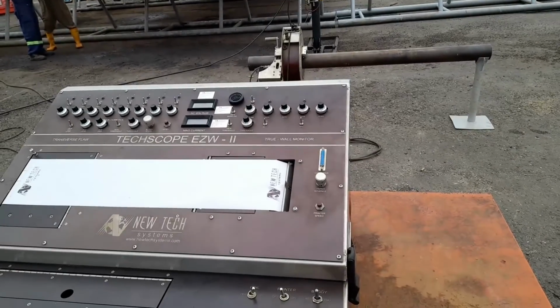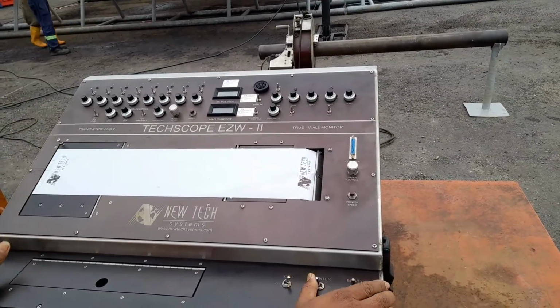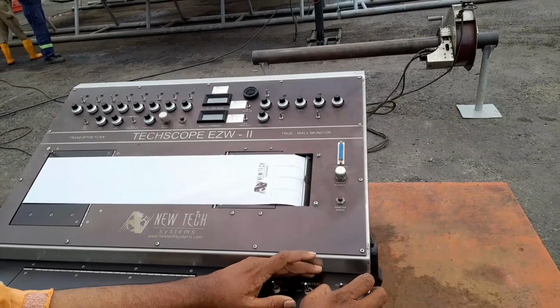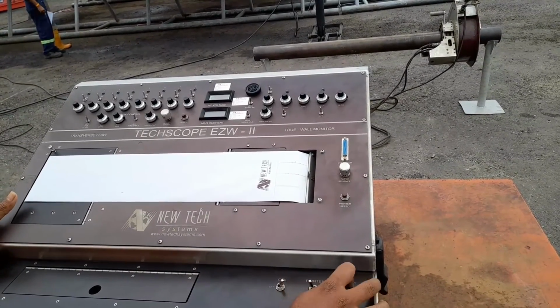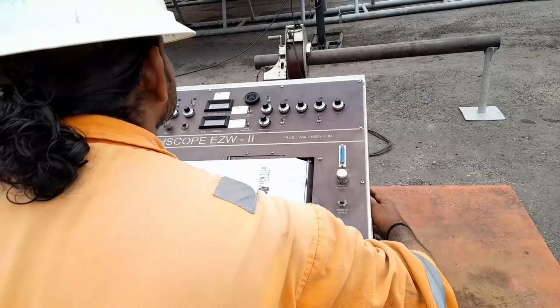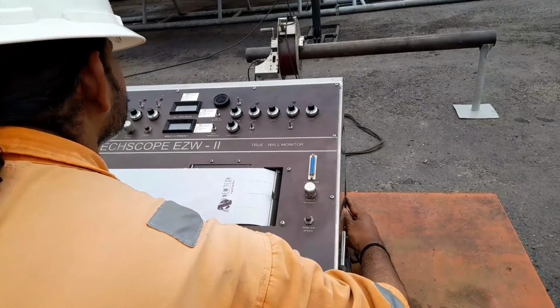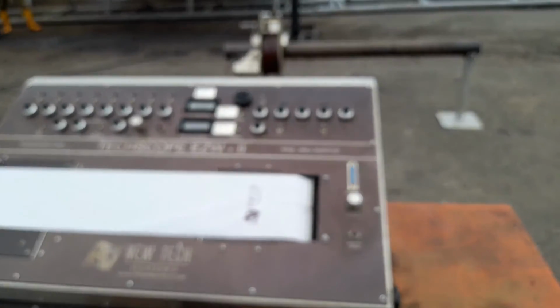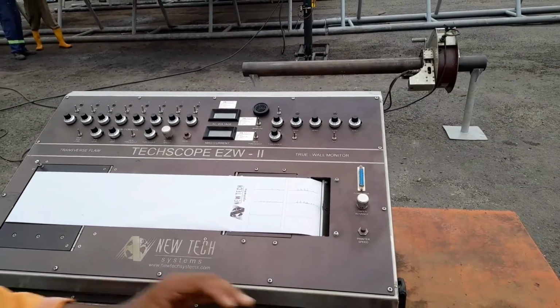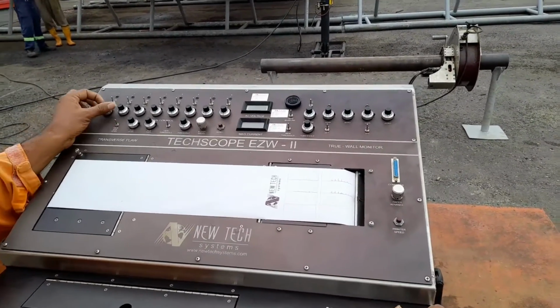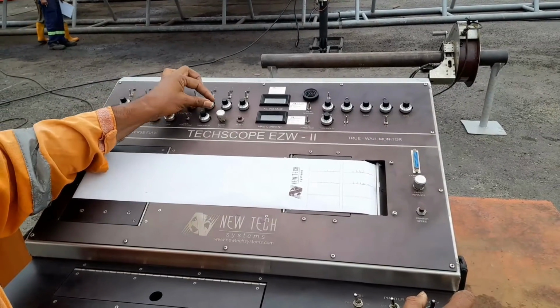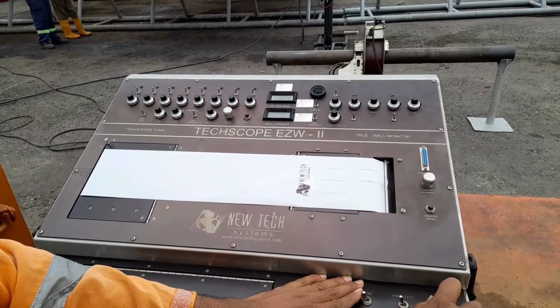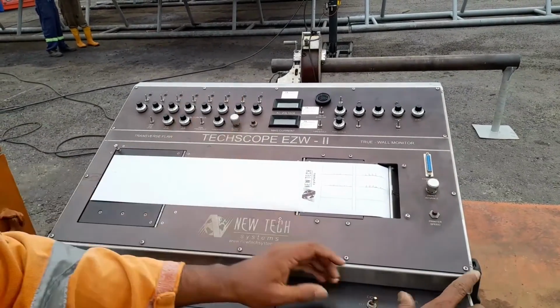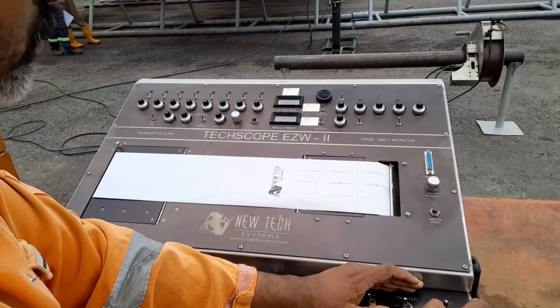So the next step is, if right now you get a single kick of 5 mm, you have to increase some value, blindly increase some value, then run the buggy head in reverse and place it at the first position. Again check the alignment of the shoe, then run again. Then you get 12 mm. So your kick point, which you assumed to be 10 mm, was 12 mm. So run in reverse again, adjust a little bit, and reduce the gain. It means rotate the control anti-clockwise, then it will reduce. Achieve the 10 mm. Again run it. It will be 10 mm. It's okay.